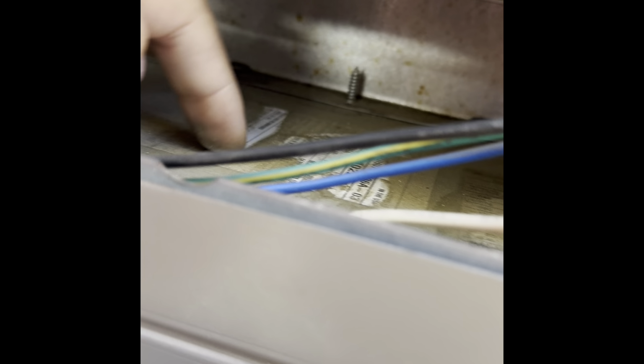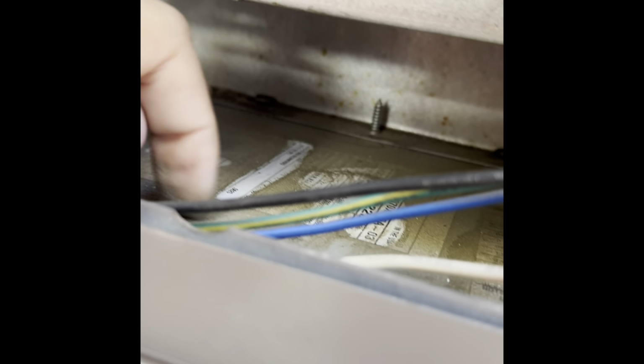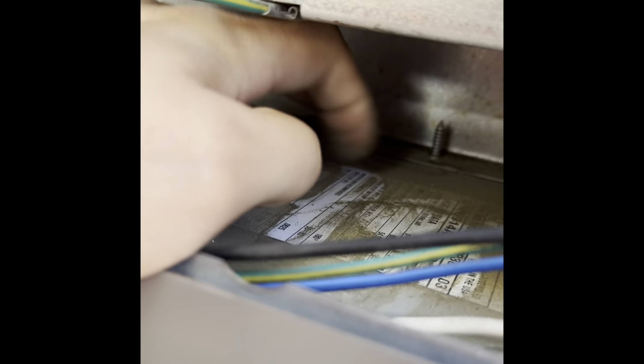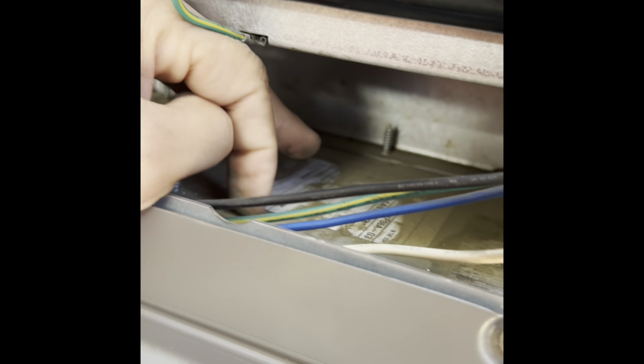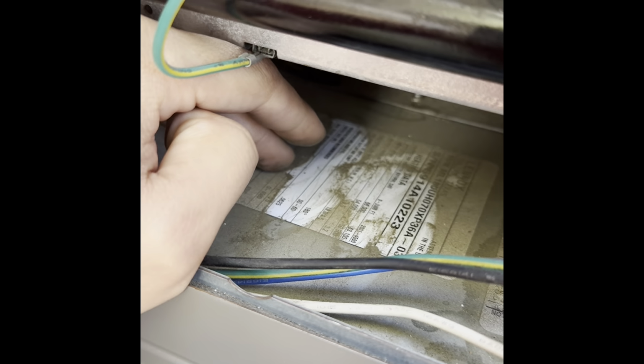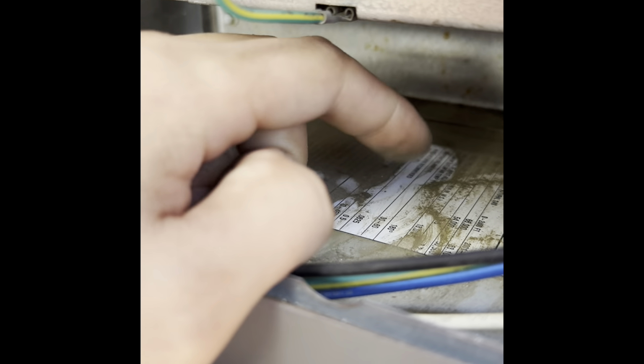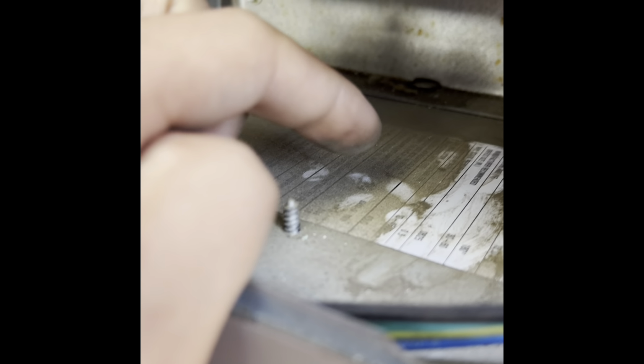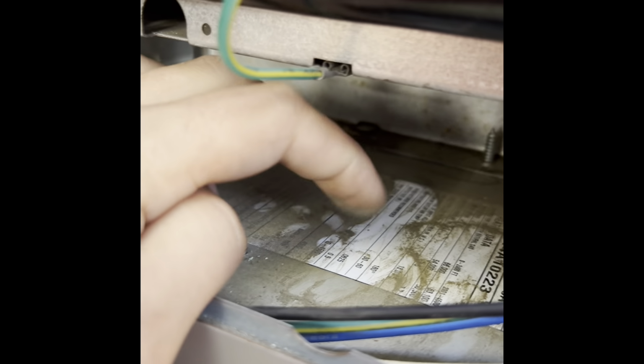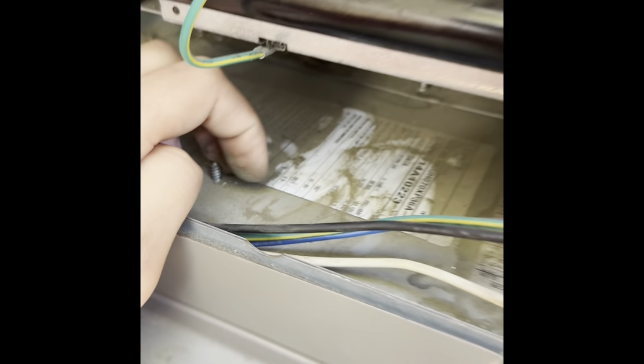Let's see, so you see this manifold, the manufacturer recommended temperature rise listed here. So this thing cannot go over 180 degrees on the supply side. And over here we see that the temperature rise can only be between 30 and 60 degrees.